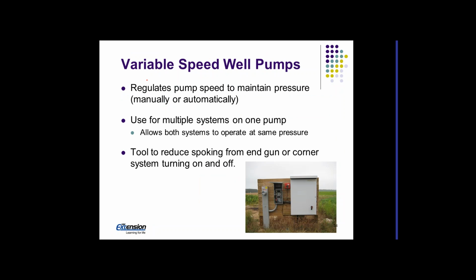Variable speed drives, they can help us. We can basically regulate the pump speed to maintain a pressure. This can be done manually or automatically. If we do it automatically, we're going to use a pressure sensor to feed back to the controller. So if the pressure goes low, it speeds up the pump. If the pressure goes high, it slows down the pump to maintain the set point.